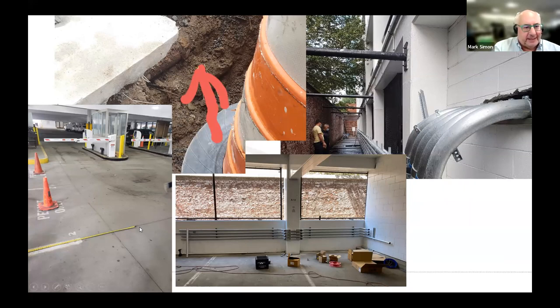We had thought about doing the chargers on the side rather than in front, but that also did not work with the space we had. Up on the top left — if you're in a dense urban environment with a lot of old stuff — as they were trenching, they found a pipe. Does anyone know what this pipe does? Can we cut this pipe? Bottom line, no one did know. We basically went underneath the pipe. You're going to get delays, you're going to get snags. This happened on my first site — expect the unexpected.